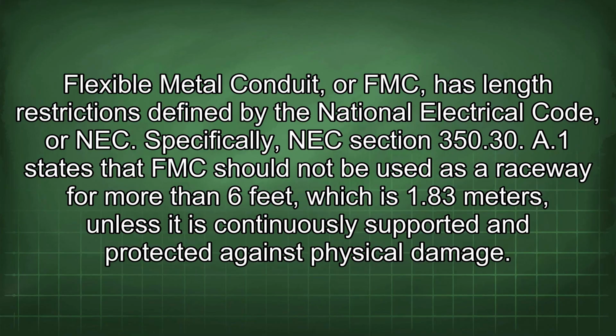Flexible Metal Conduit, or FMC, has length restrictions defined by the National Electrical Code, or NEC. Specifically, NEC Section 350.30(A)(1) states that FMC should not be used as a raceway for more than 6 feet, which is 1.83 meters, unless it is continuously supported and protected against physical damage.